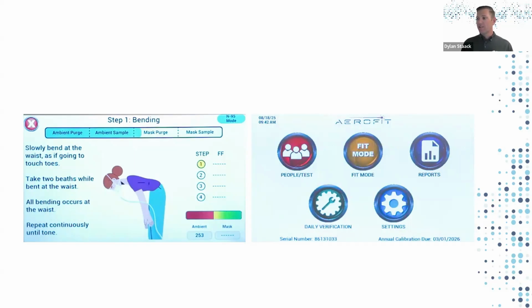If you look to the right, you'll see what it looks like when you turn your AeroFit on. These are the 5 tiles that are on there: people test, fit mode, reports, daily verification. So we have written and visual instruction there, or navigation, which makes it super simple. If you're used to looking at a QuantiFit 2, you're going to turn this on and notice that it's very similar. It's not identical because there's a little bit of difference in the technology, but if you can navigate one, you can navigate the other.